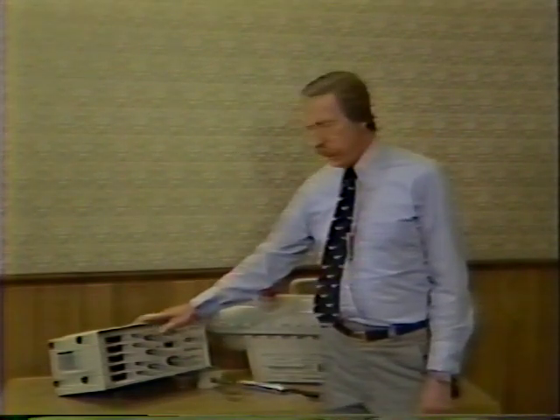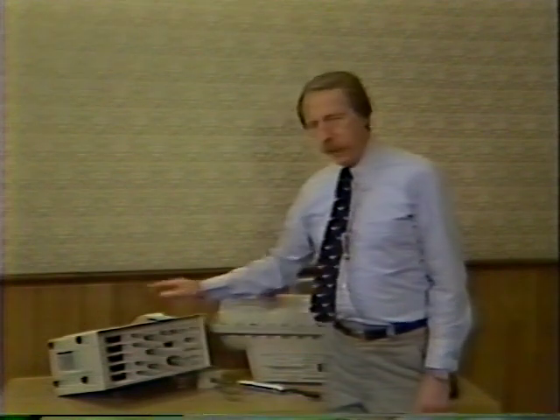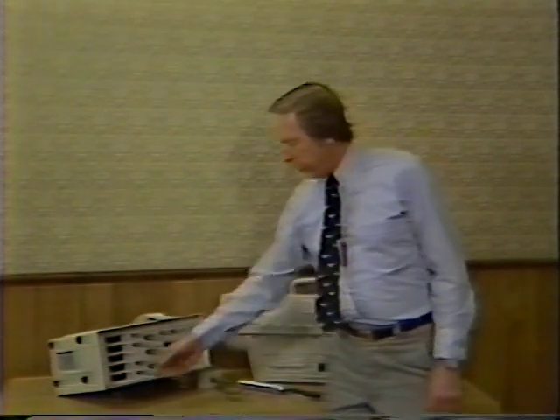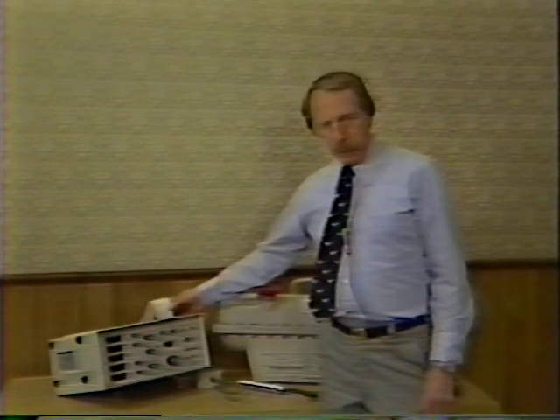Remember, this is a microprocessor device. Since we have the data available to us, we can then calculate mR per second and mR per mAs. All of these can be printed out on hard copy on this unit. On the last display, you're going to read line voltage drop. We also print out the percentage of line voltage regulation, since that is a BRH requirement during compliance testing. We're now ready to go to the next slide to see the data that's been made available to us on the first exposure. Data obtained on the first exposure is peak kV, mAs, mA, time, mR, mR per second, mR per mAs, standby filament current, boost filament current, no load line voltage, loaded line voltage, and we print out percentage line regulation and kiloheat units per exposure.